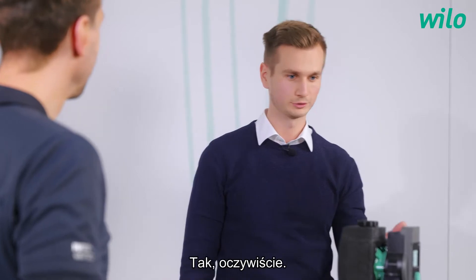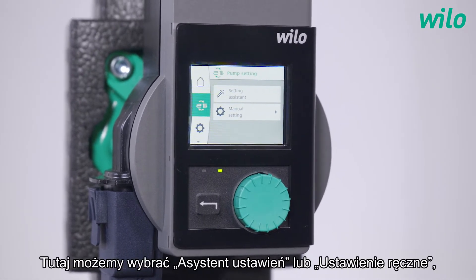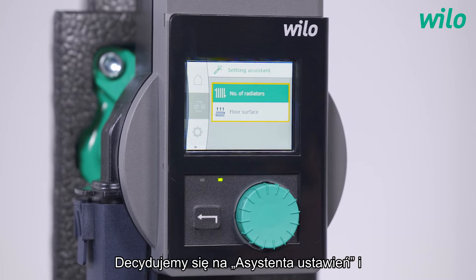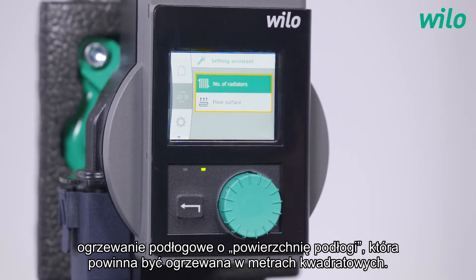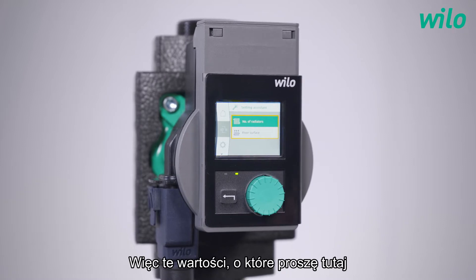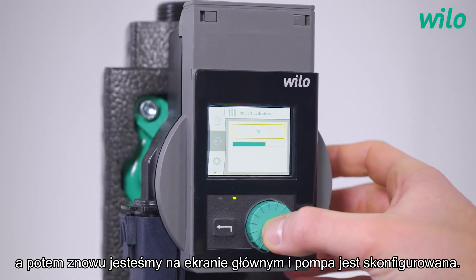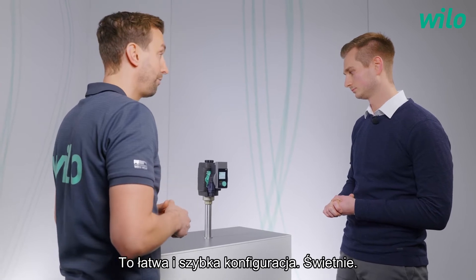How is it done? Could you show it? Of course. We just go to the menu 'pump setting' with the help of the green button. Here we can select either the setting assistant or the manual setting, where typical control modes like dynamic adapt plus, delta pv, delta pc, or constant speed are selectable. We decide for the setting assistant, and now we are asked for the number of radiators — or in case of underfloor heating, for the floor surface area that should be heated in square meters. With these values that are asked for, really everyone has them right to hand. When we select number of radiators, we can just turn the button, intuitively select the value, and then we are in the home screen again and the pump is set up. This procedure is also applied for underfloor heating of course. That's an easy and fast setup.